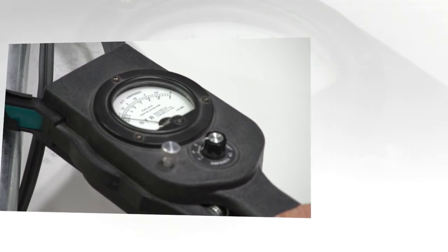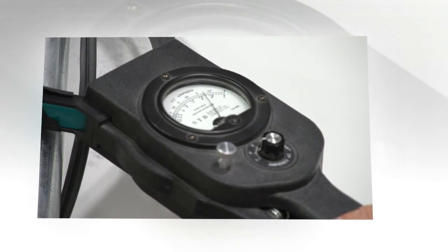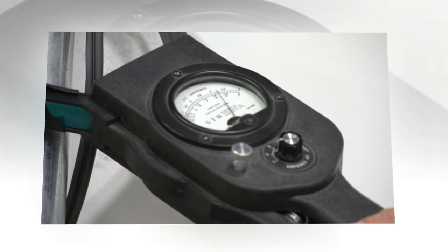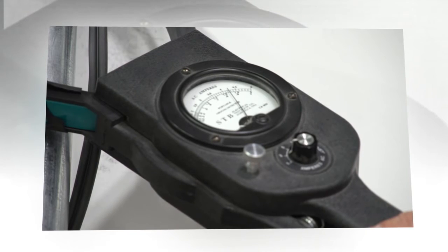So when a ground fault occurs, I can use this current clamp that's going around the entire conduit. And when a ground fault occurs, the return current doesn't all go back up through the same ground path. It's kind of like a GFI in your bathroom in your house, where the current that goes in on the hot doesn't necessarily return on the neutral.